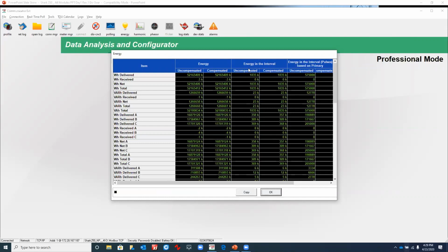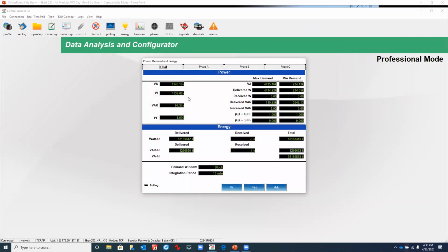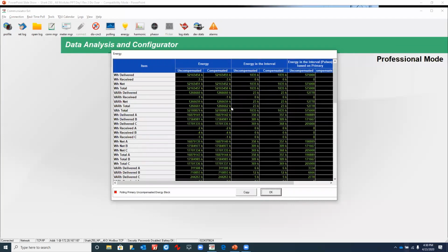This column here is called the energy in the interval, the amount of energy that's stored per interval. So if a meter is 15 minute intervals, that's 4 intervals per hour, and this value would be 4 times that value. If I looked at 1035 and multiplied it times 4, I would see approximately 4 megawatts in the polling. So it's about 4 megawatts there. But basically, the energy grid is just another way of viewing, making sure you have all your energy values.